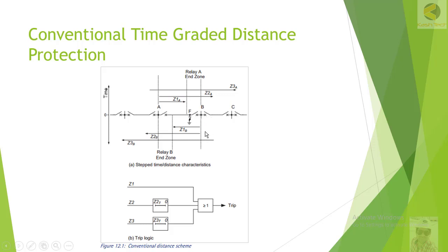For example, if the fault is just beyond Station B, the relay at B trips in Zone 1. If Station B's relay fails to trip for any reason, the relay at Station A will trip in Zone 2, which is again 250 to 400 milliseconds. Similarly, if there is a fault just after C, Station C should trip fast. If Station C's relay fails, Station B trips in Zone 2, and if Station B also fails, Station A trips in Zone 3. This is the concept of graded protection — it is not unit protection.